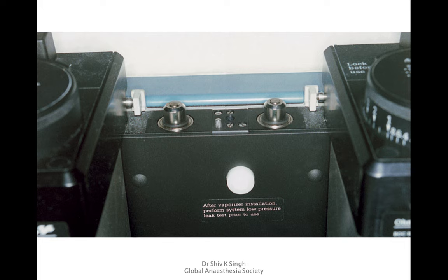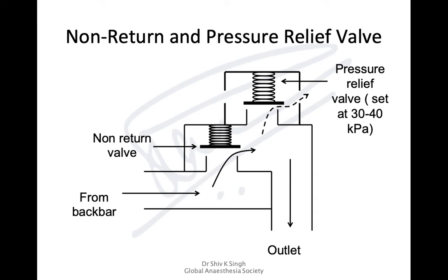Next is the back bar, where you find the vaporizers and vaporizer seating. The O-rings on the seating are important as they can lead to leaks during machine testing and need to be checked. On the back bar there are also non-return valves and a pressure relief valve. If back-bar pressure increases, the non-return valve shuts off to prevent damage or backflow into the vaporizer. If the common gas outlet is blocked, the pressure relief valve releases gas — set at around 30–40 kPa.